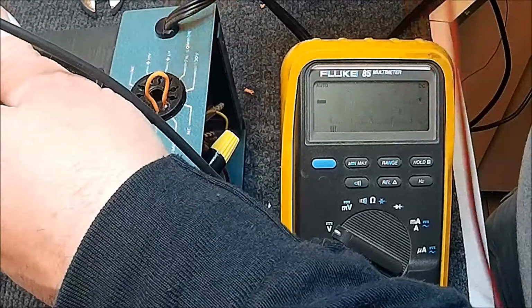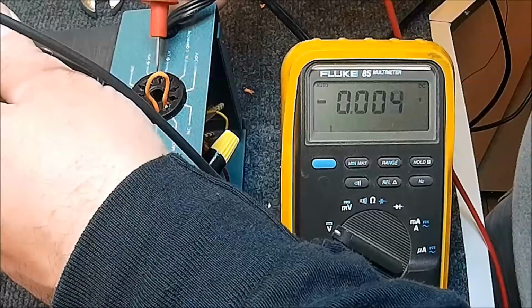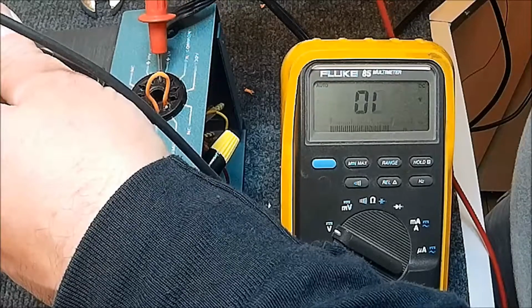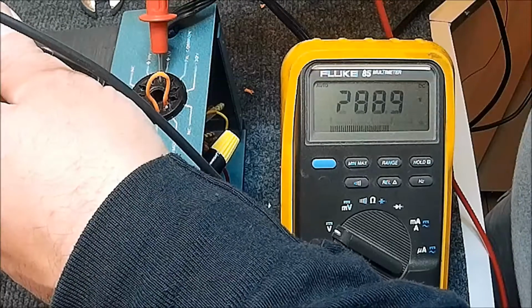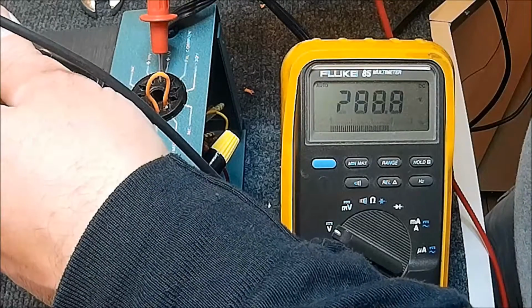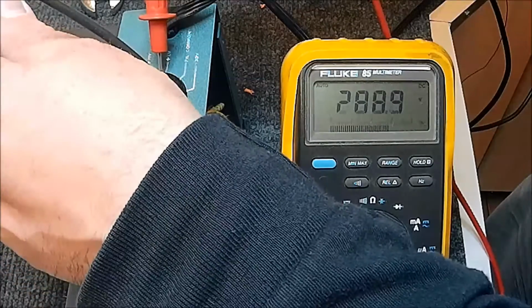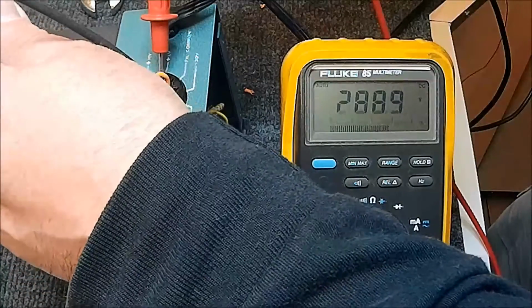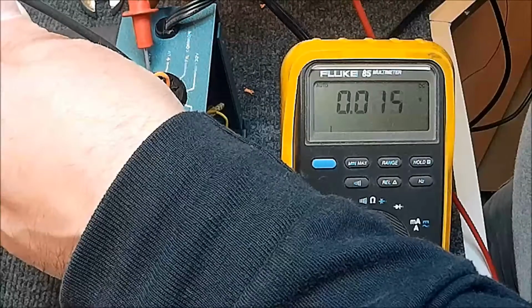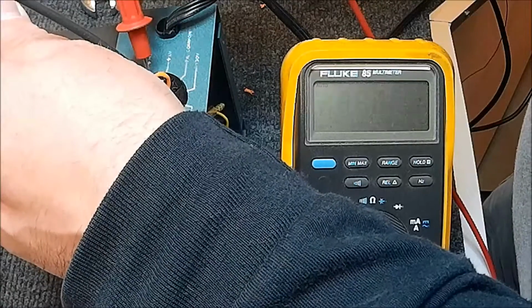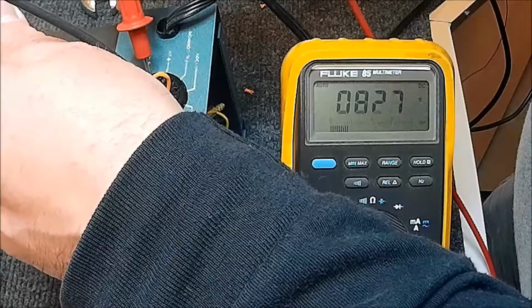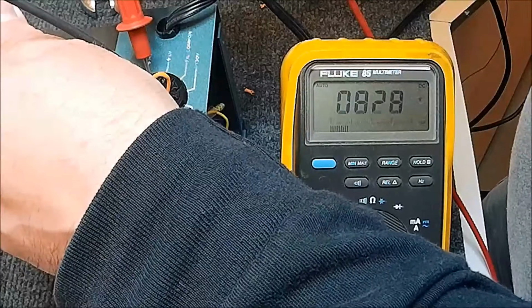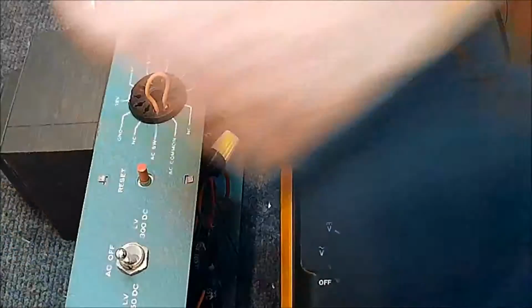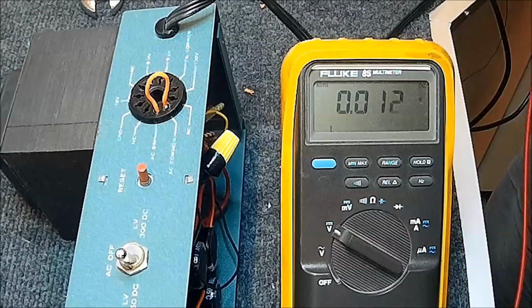Then we check the low voltage tap, and look at that, we've got 289 volts. On our high voltage side, we have 828 volts, which is right on spec. It says 820 is where it should be.